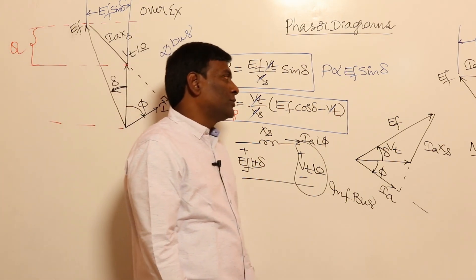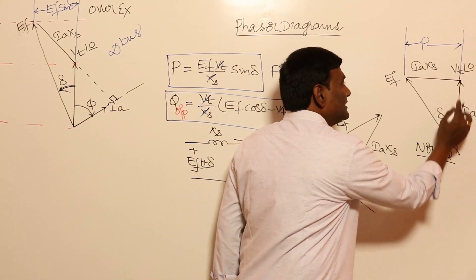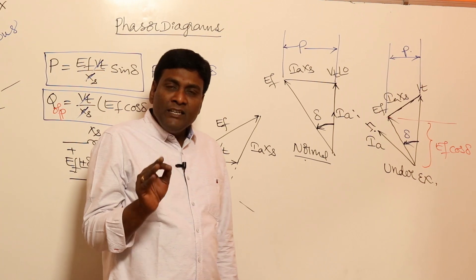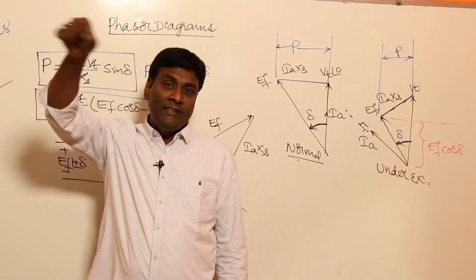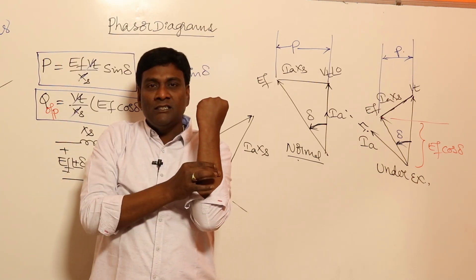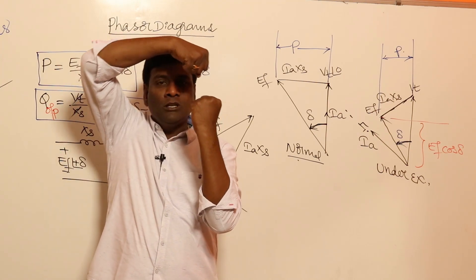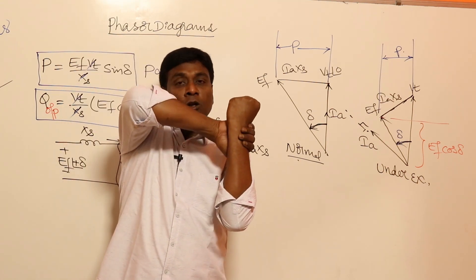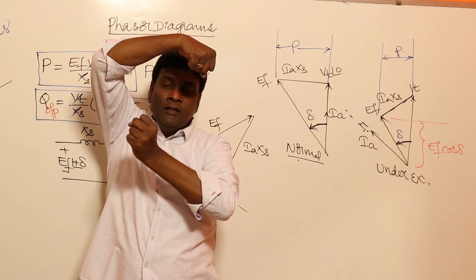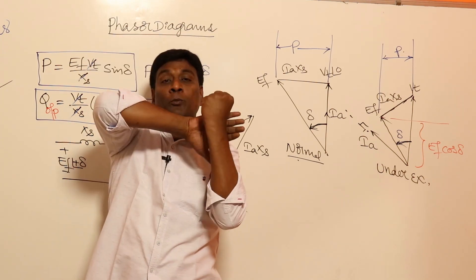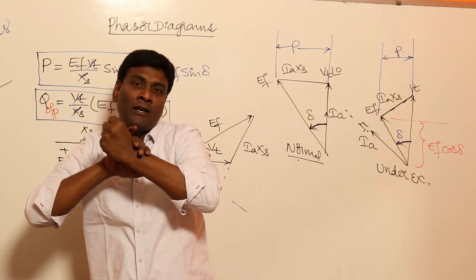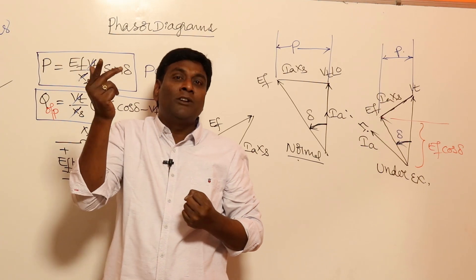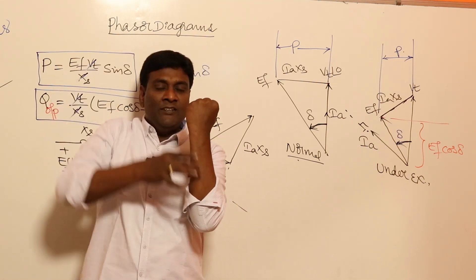One final conclusion: Ef always leads Vt in a generator (alternator). This is because if the field pole is ahead of the resultant pole, both rotating in the same direction, there is a back torque, but the prime mover resists this and converts mechanical energy into electrical energy. So the field pole must lead the resultant for generator action.